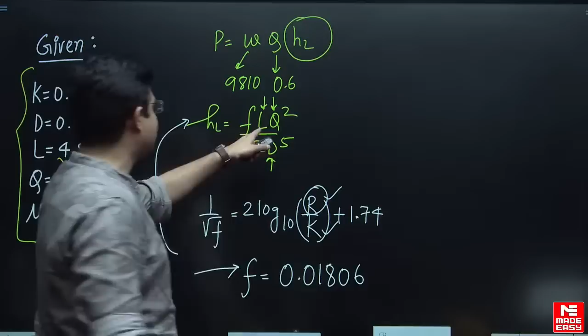So from this particular thing you are going to find out the friction factor. According to my calculation, you can always cross verify, the friction factor will come out to be 0.01806. Once you put the friction factor in this, you are going to get the value of head loss. According to my calculation, this is 0.01677.